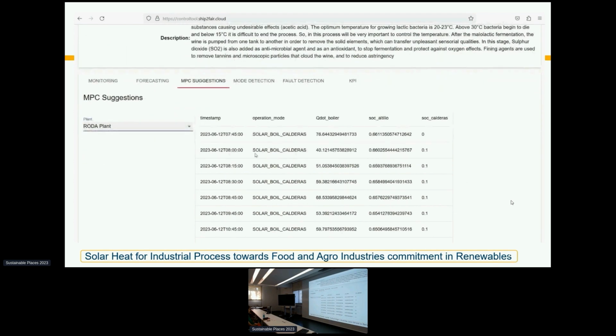For example, it recommends you run, for the next time steps, the operation mode called solar boiler, so solar preheating and then using a gas boiler. It also tells you about the storage, the amount of energy you should produce by the boiler, and the state of charge of two of the storages existing on site.